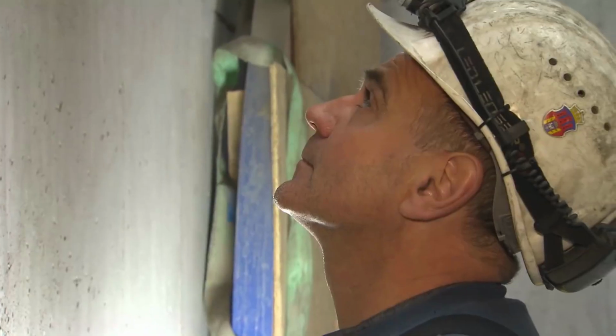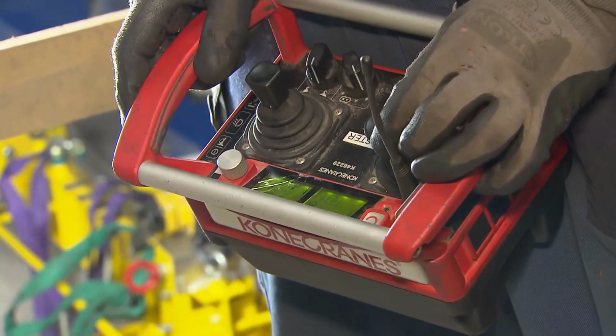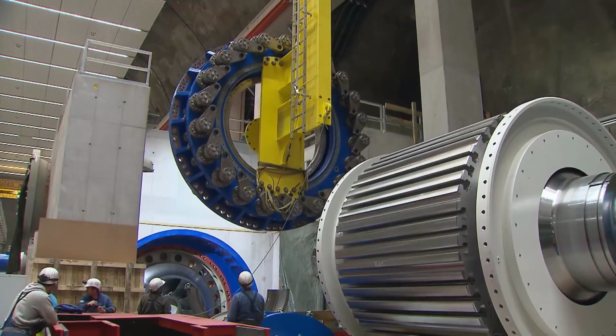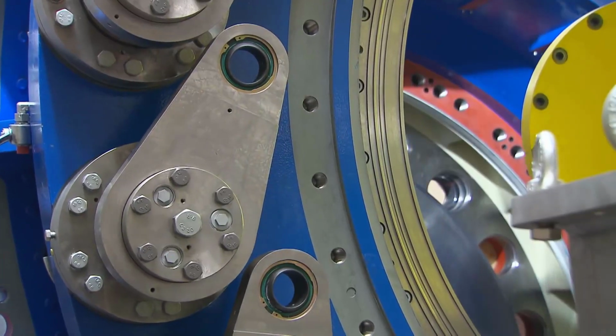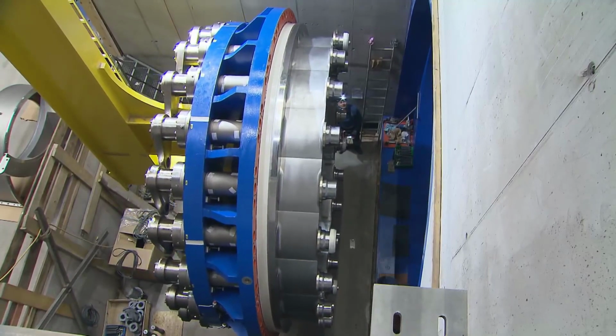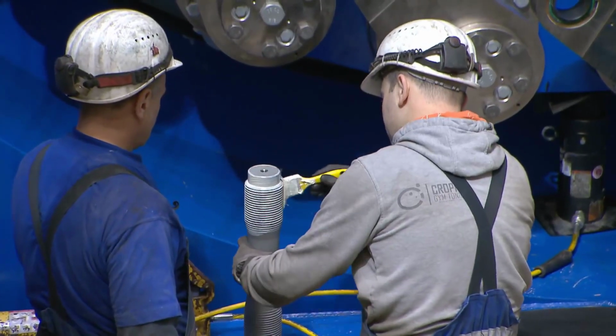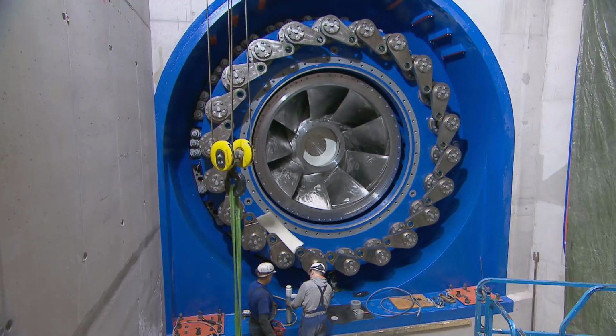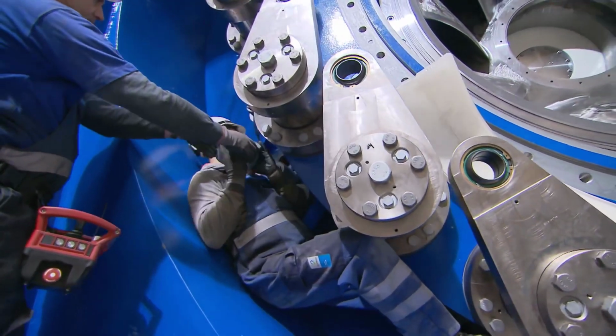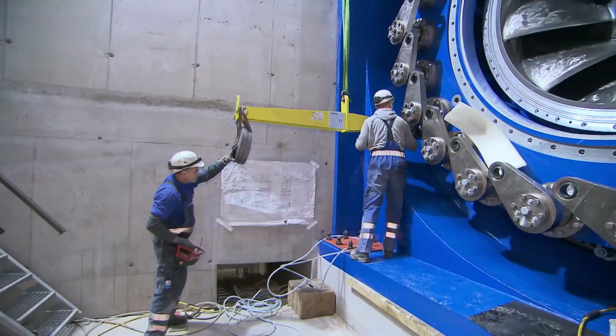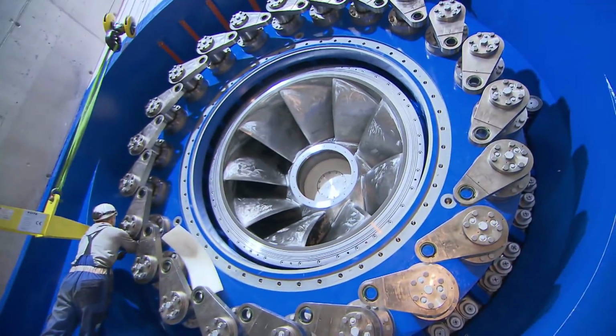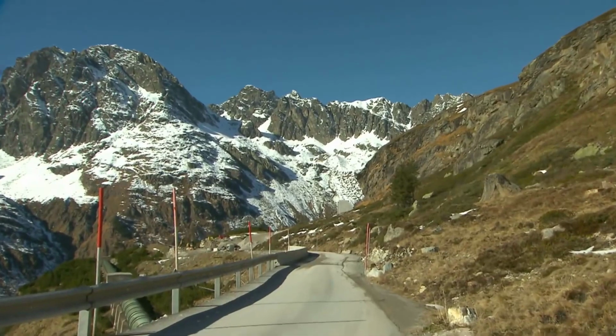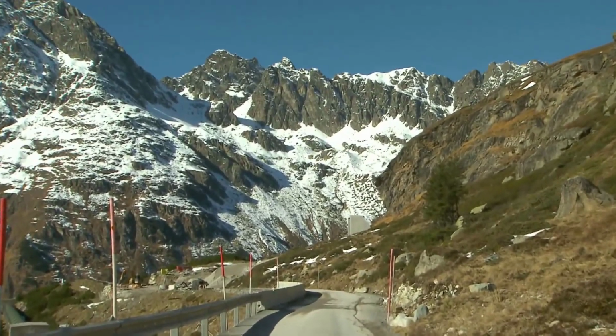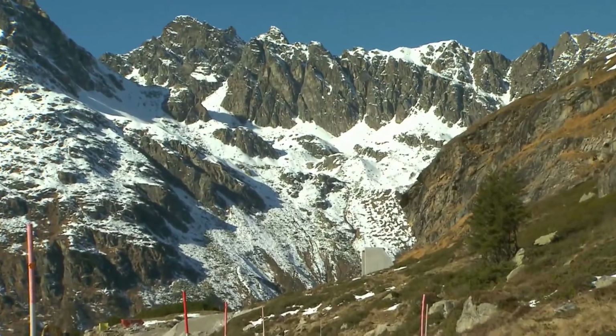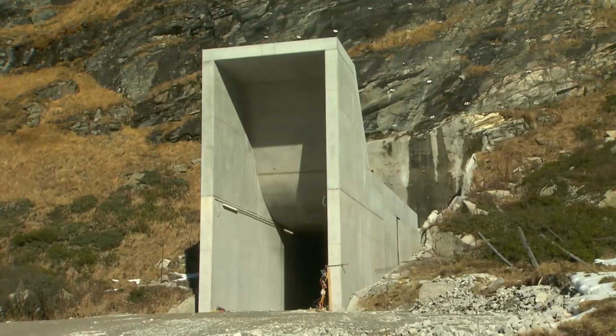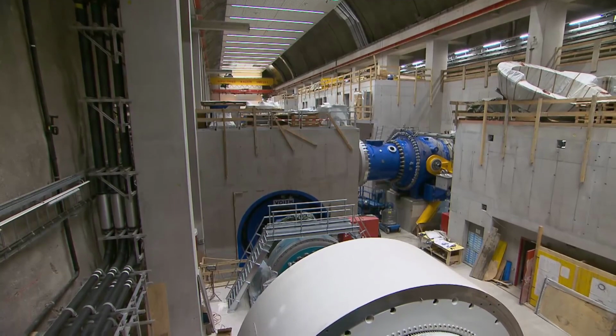Overall, the Obervermuntwerk II project has come significantly closer to completion in its fourth year of construction. In some areas, such as the portal and ventilation structure of the water castle, the condition has already reached the anticipated state post-completion. In the cavern, the machine's sluice valves, expansion pipes, control technology and much more have been assembled to the extent that the runners are already turning. Soon, they will no longer be visible, as commissioning work on the machine set will begin in a few months, allowing the power plant to commence operations by the end of 2018.